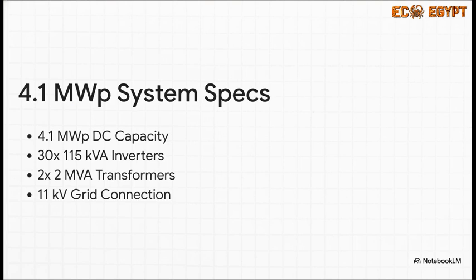And finally, Section 4, the 4.1 MWP grid-connected giant. Just think about the sheer scale of these numbers for a second. We are dealing with 4.1 megawatt peak of DC capacity converted by an astounding 30 individual Huawei 115 kVA inverters. But obviously, you can't just plug that much raw power directly into the national grid. It has to be aggregated and stepped up through two massive 2 MVA transformer stations. That pushes the voltage way up to an 11 kilovolt grid connection via dedicated ring main unit skids.